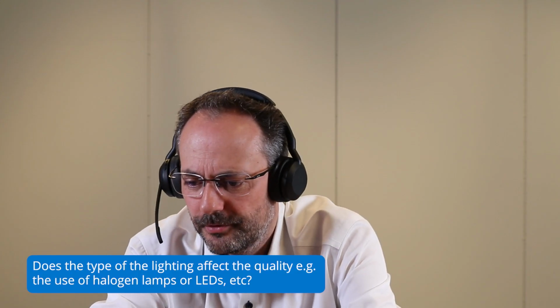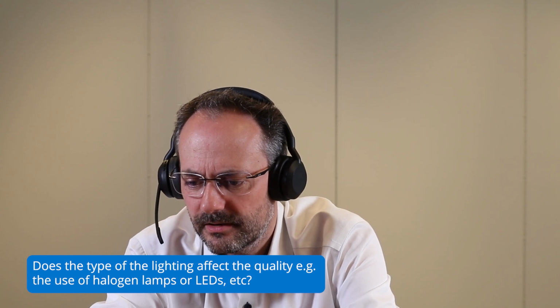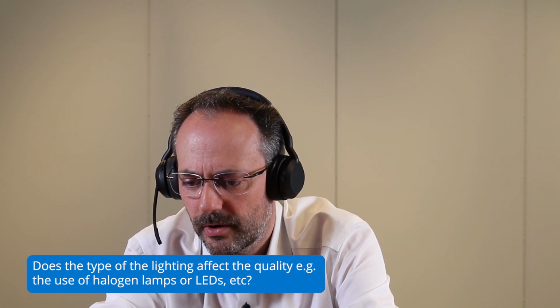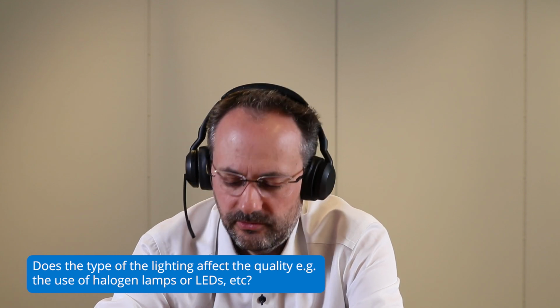Does the type of lighting affect the quality, e.g. the use of halogen lamp or LED, etc.? Well, yes, you first of all need to use a light which is suitable for hyperspectral imaging, because when you measure reflectance with the camera, you need an incoming light covering the full spectral range. If the incoming light has some dip or hole within the spectral range, you cannot have reflected light at those wavelengths, so you cannot measure a spectrum. So it's important that you have a light which is suitable for hyperspectral imaging.